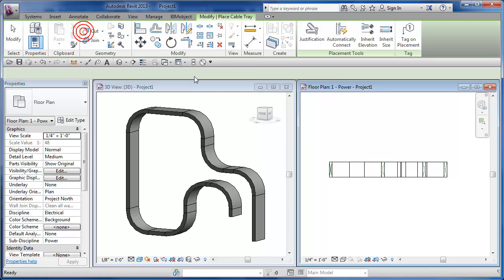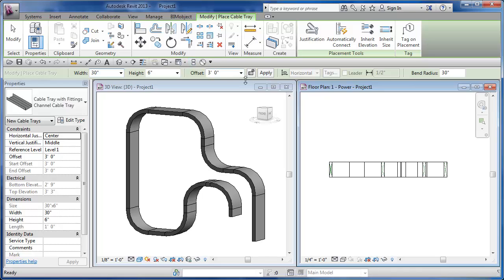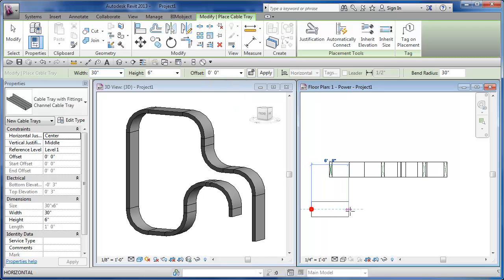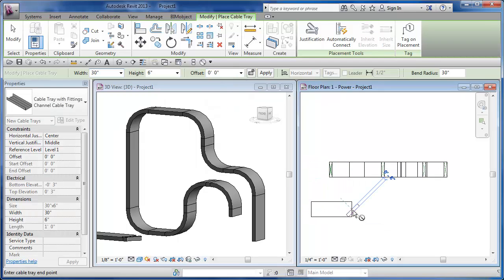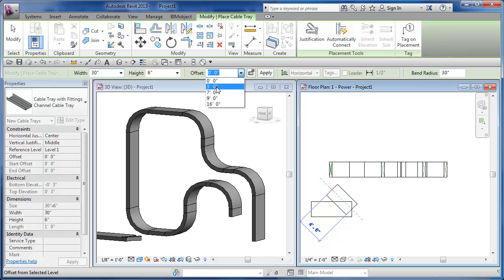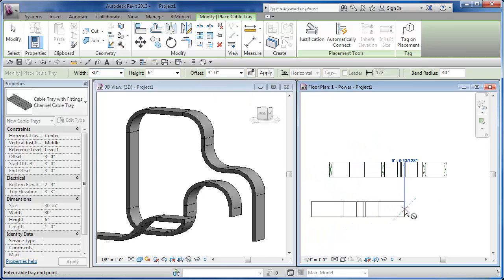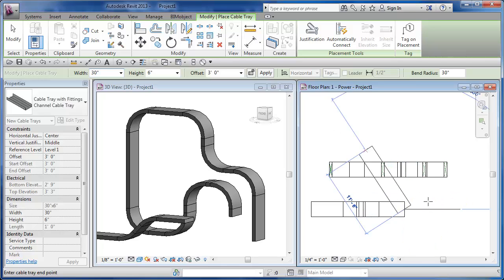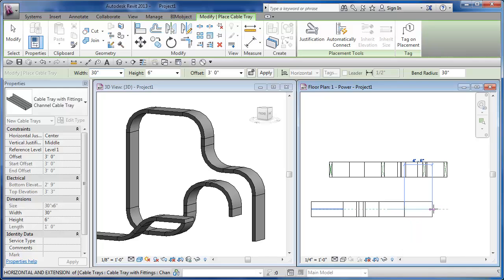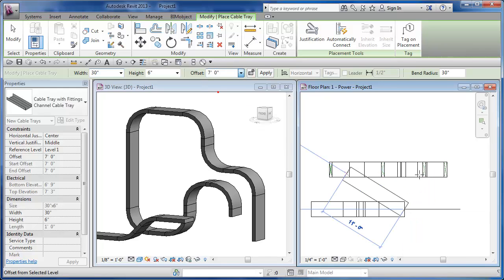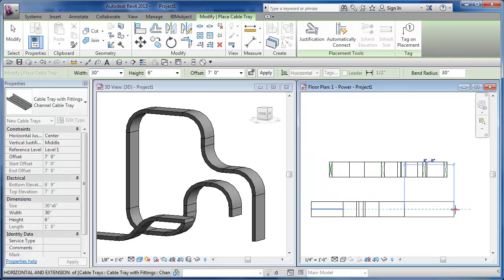Doing it in plan view and changing the heights that way is quite easy. We can start cable tray at zero, go to a point, then change the offset to three feet and go to another point — it'll actually put that rise in. After we're at three feet, we need to provide enough room to do that transition, and then we can go to seven feet over here. It puts that transition in.